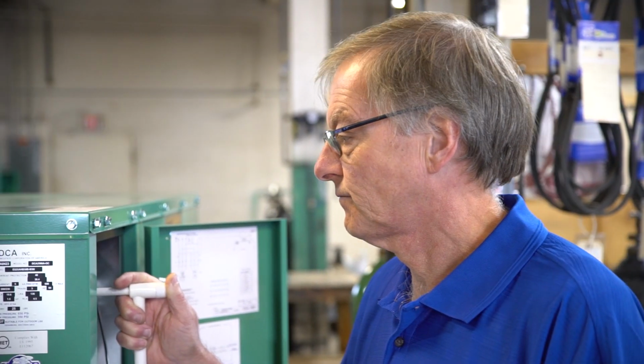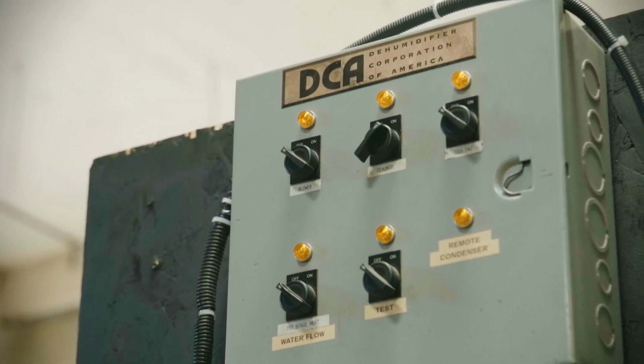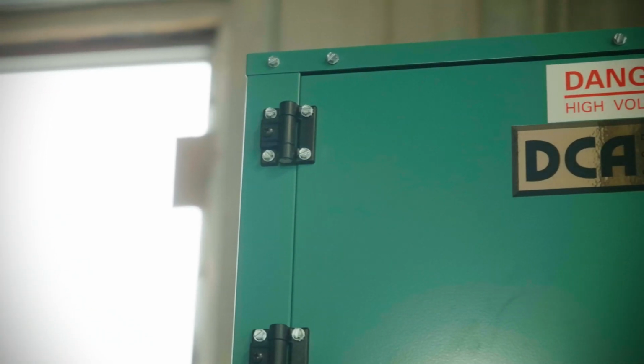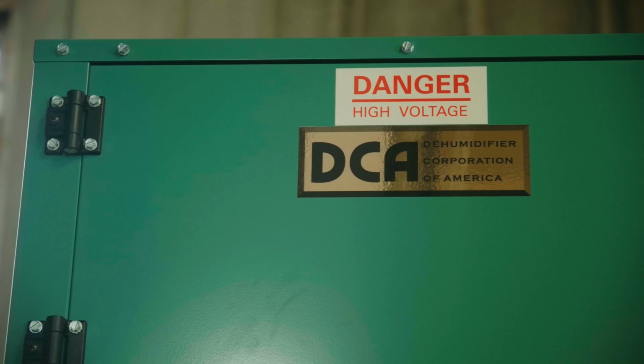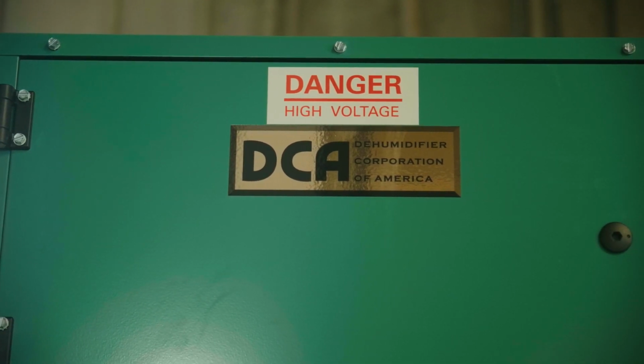Then we also run it on high head pressure and check all the controls to make sure they're all working. We generally run the dehumidifiers for about an hour, maybe a little more, depending on the season, just to make sure everything's functioning properly. They tend to run a little different when they're wet versus dry, so we try to get a little bit of both. And then we also do a third and final leak check after we run the unit, just to make sure there's no freon leaks.